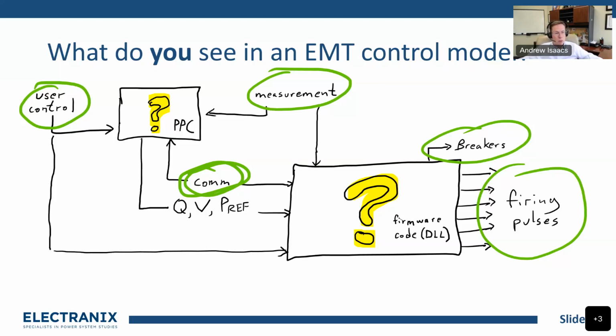But the real reason we're pushing on this now is that it used to be the inverter control did all the fast stuff and the PPC did all the slow stuff — if there's a fault, the PPC just put its hands over its ears. This is no longer true. These communication links are becoming very fast, in some cases pushing much less than a second, and functions we initially attributed to the inverter are now being taken up by the PPC.